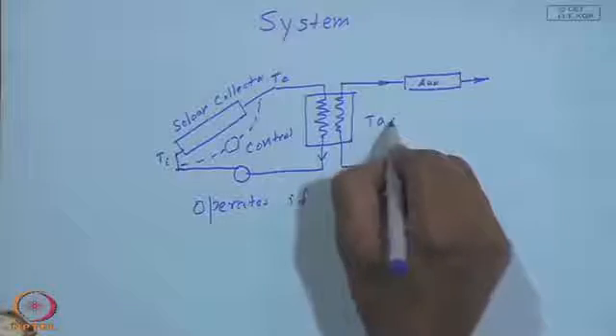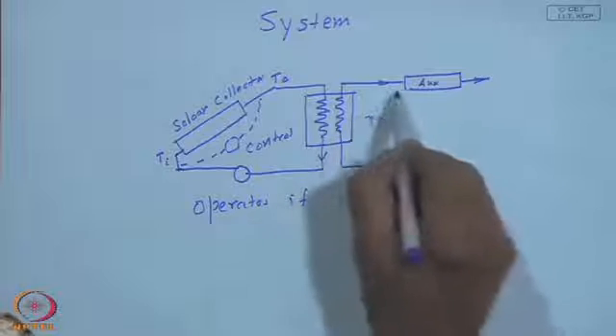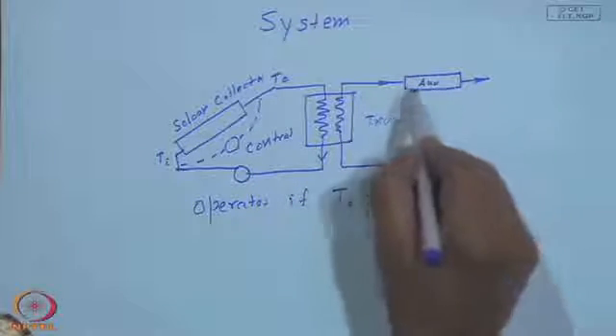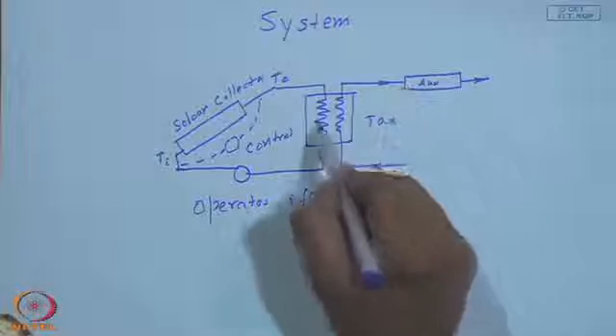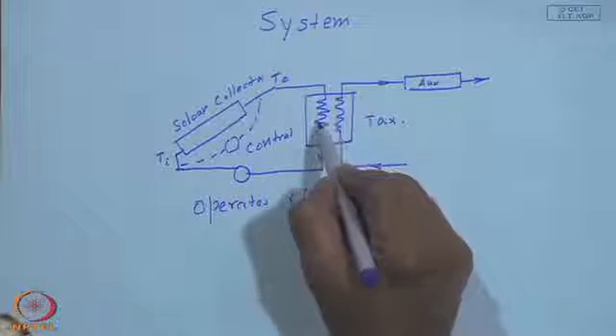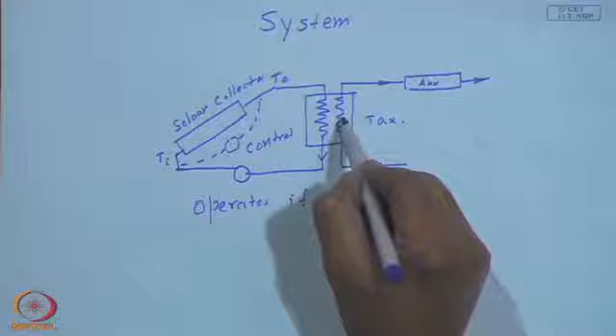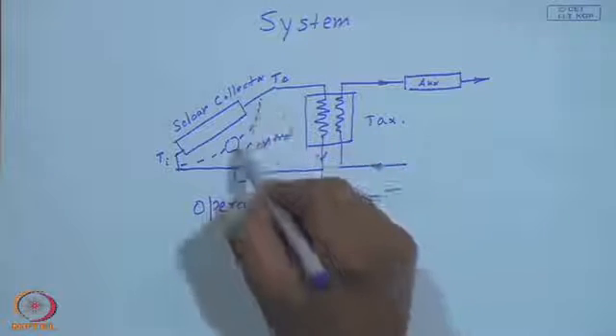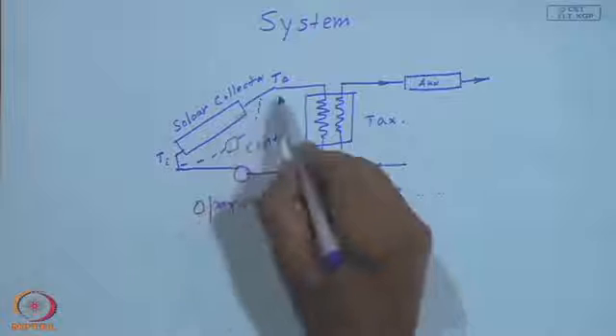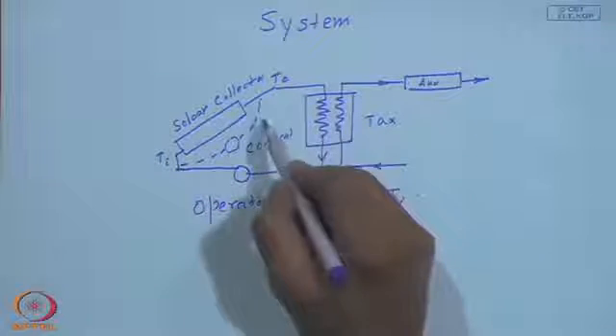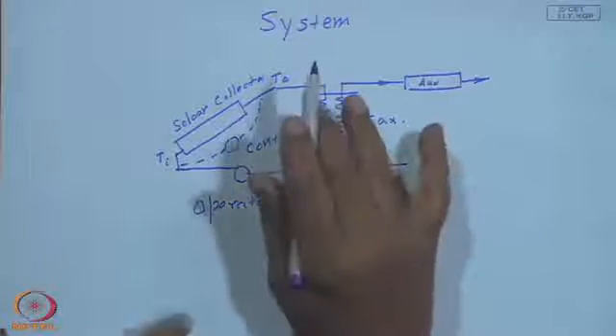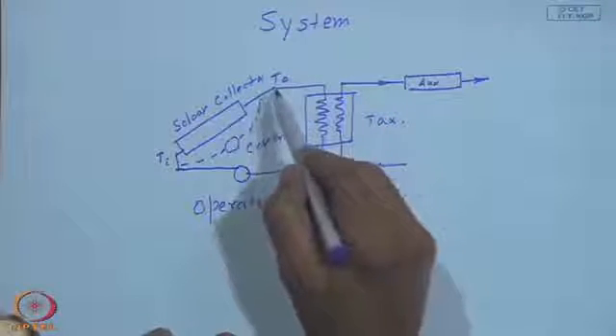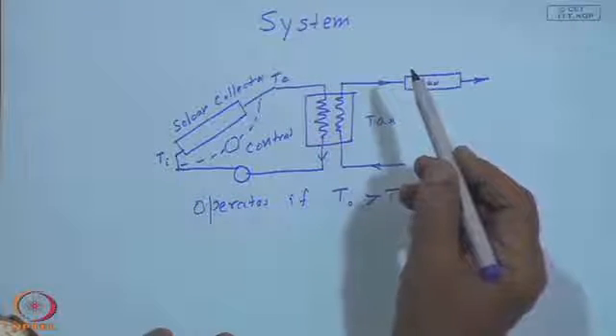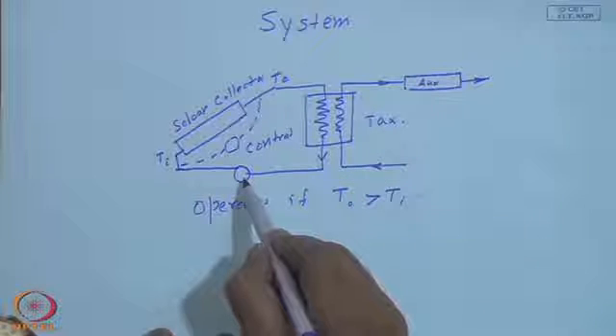Even in this simplest conceptual system, the delivery temperature, ultimately before or after the auxiliary, depends on how effective the heat exchanger is. Similarly, if the control is ineffective it may throw out a lot of cold water, or if it is too stringent, it may not send water in unless the temperature rises well above the set or required temperature. One can also expect failure of the pump.